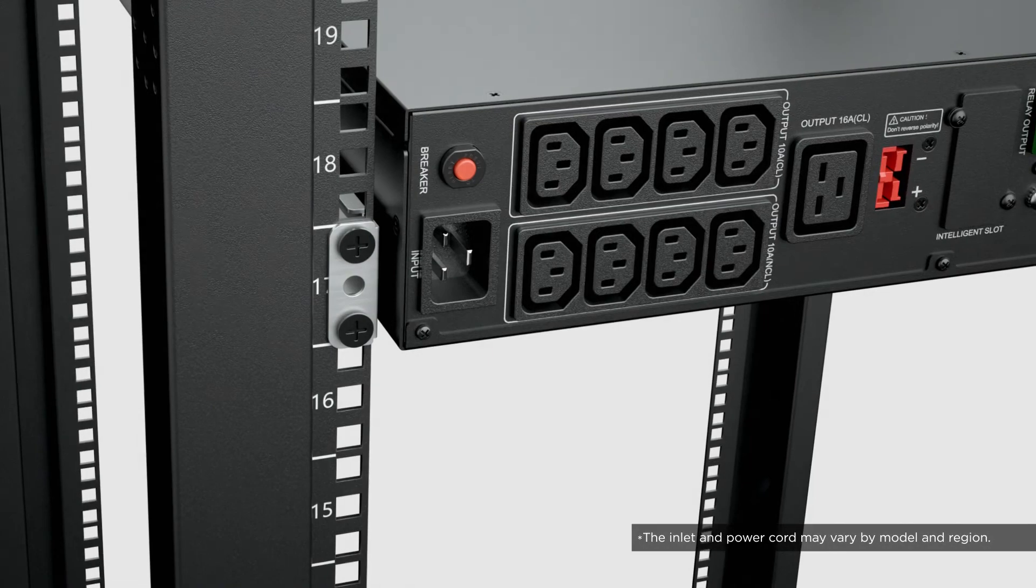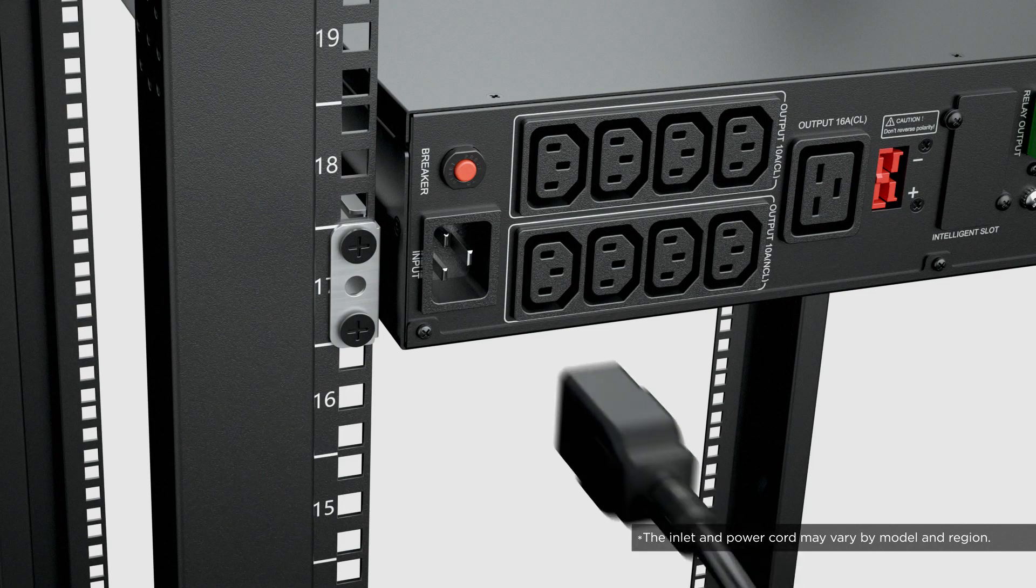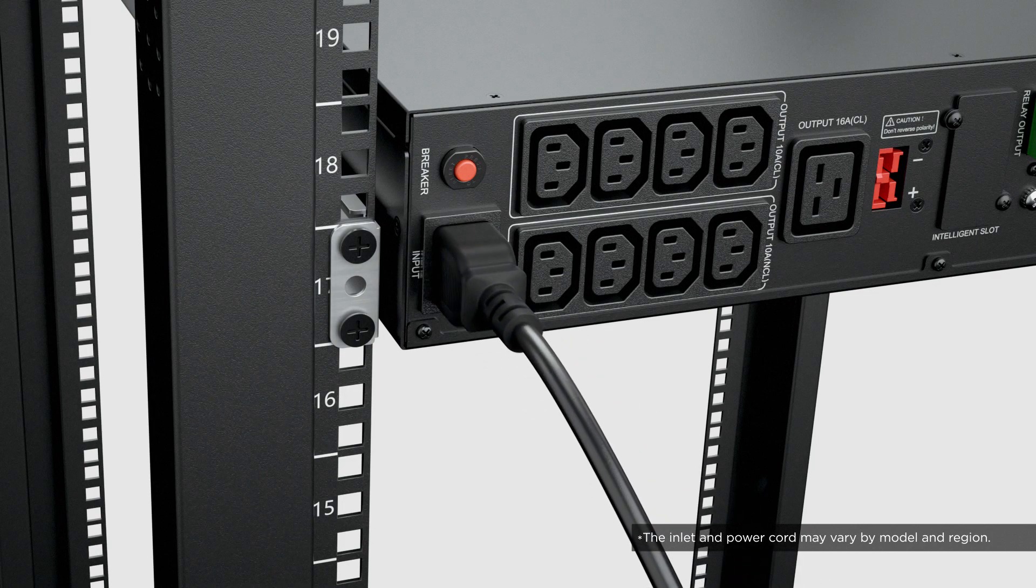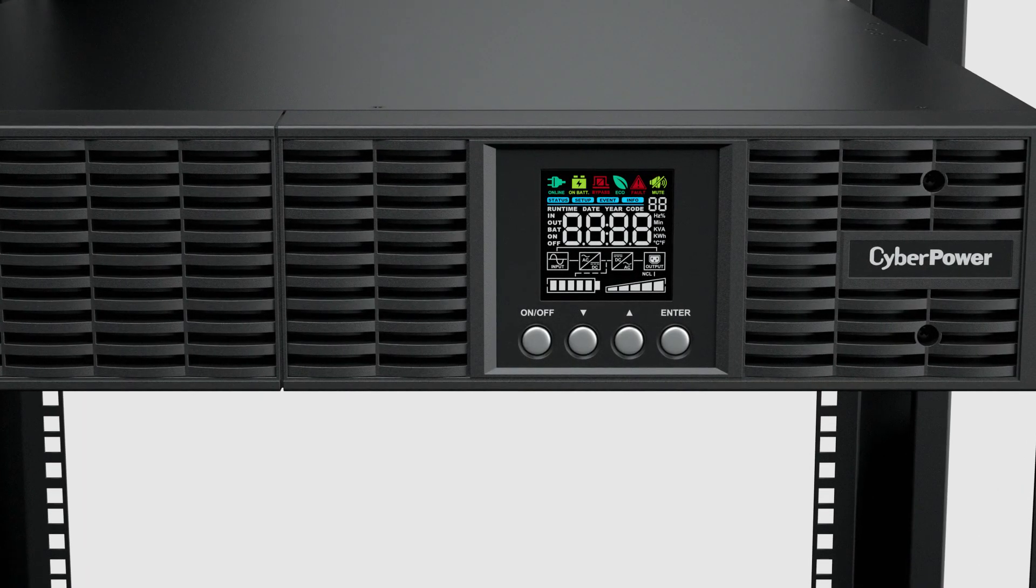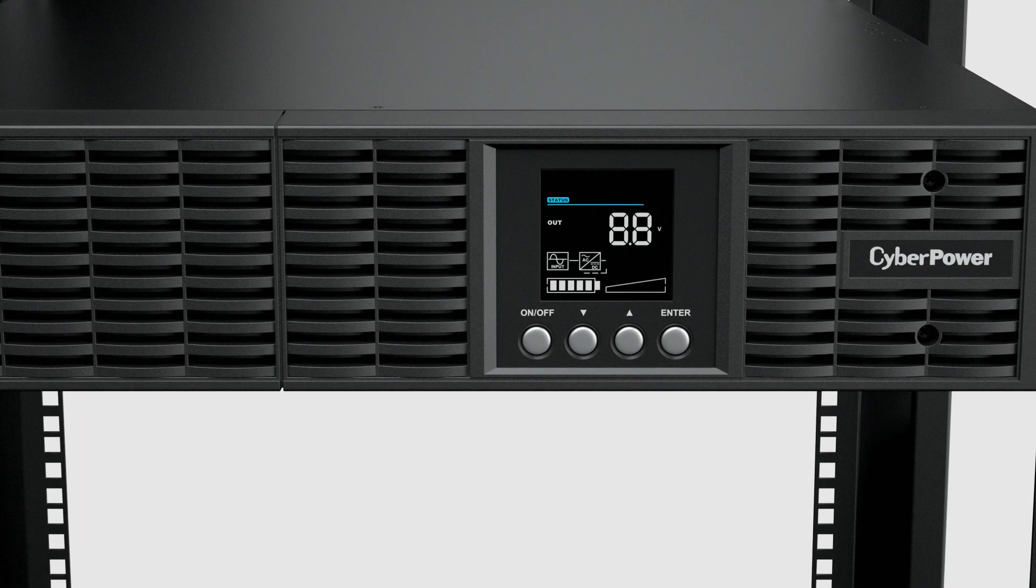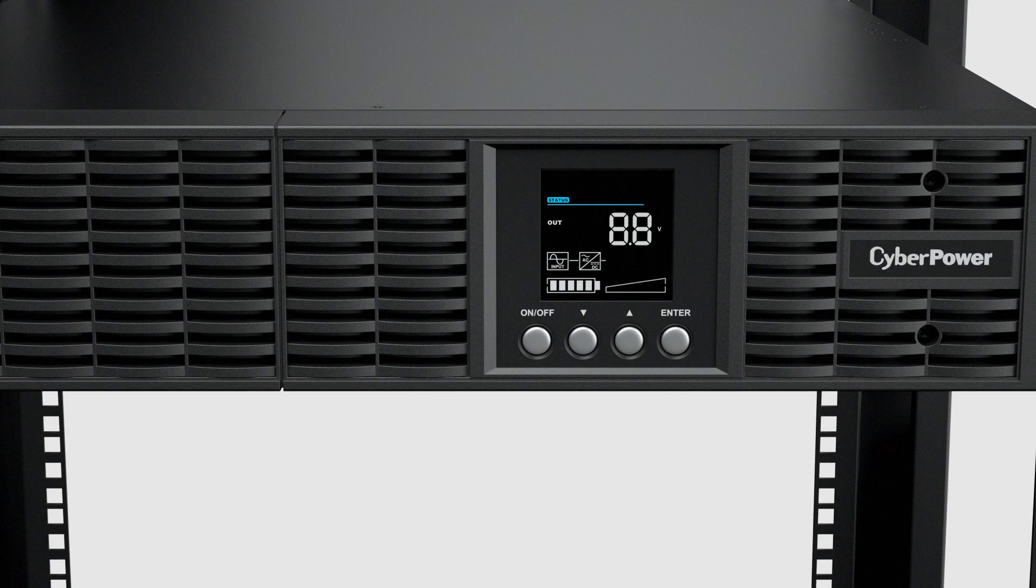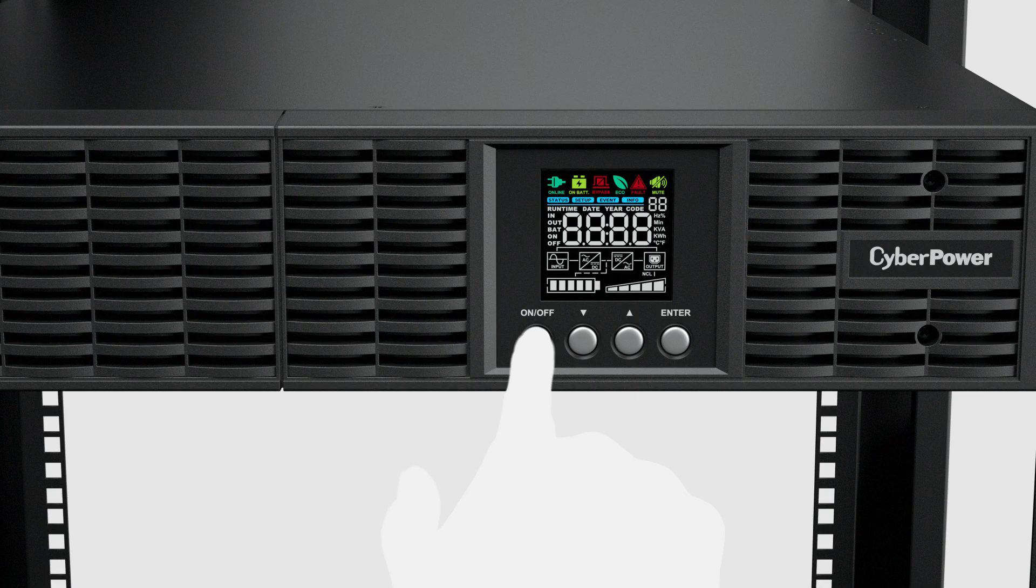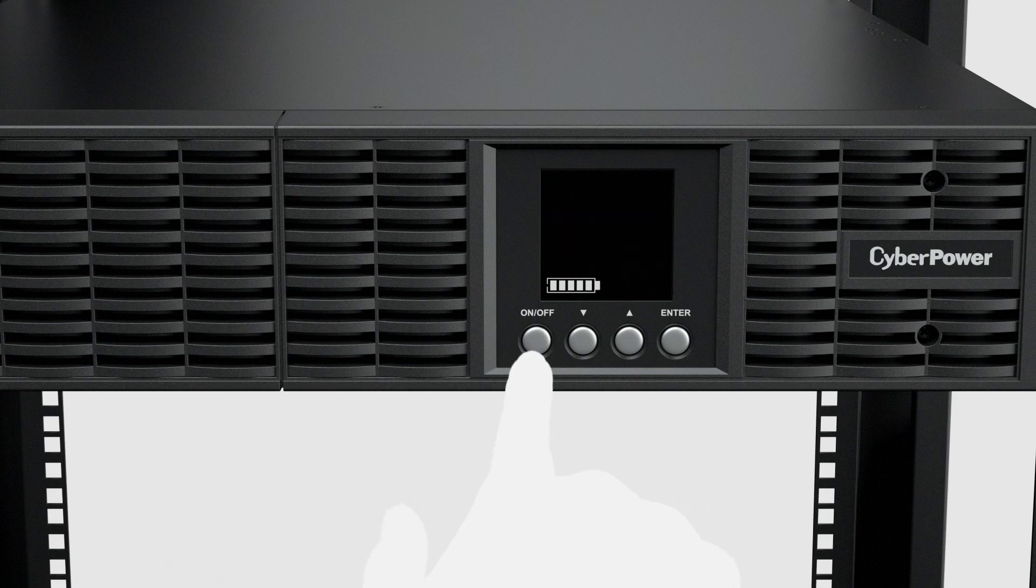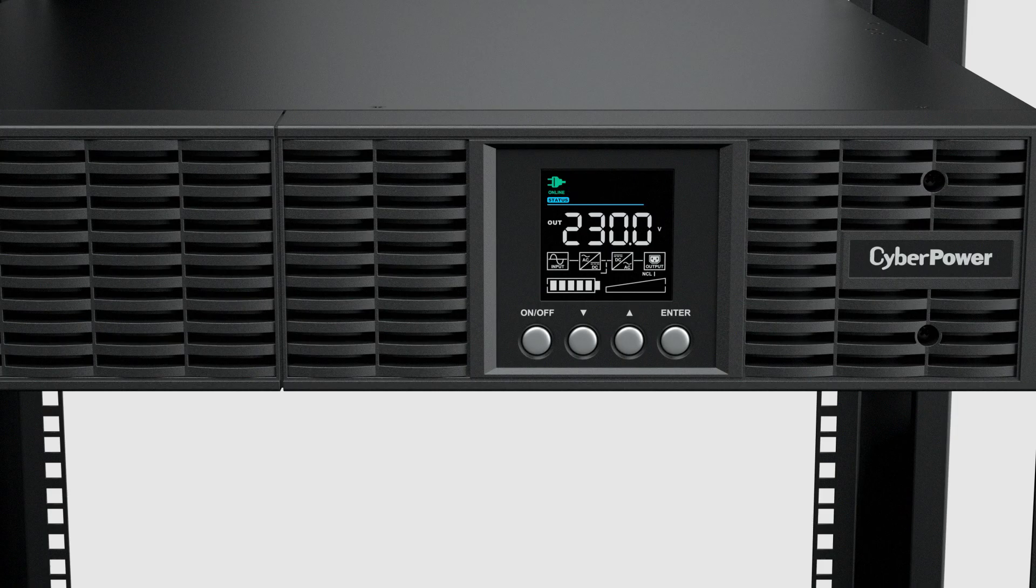If the extended battery modules are not required, plug the power cord to the UPS and the utility grid. The LCD will turn on and the UPS is in standby mode. To complete the installation, press and hold the power button for three seconds to turn on the UPS. The UPS will run a self-test and operate in battery mode first, which may take a few seconds, then transfer to line mode and is ready for use.